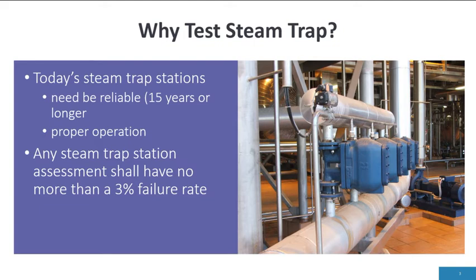So why test steam traps? Steam trap stations need to be reliable — 15 years of operation or longer at any pressure lower than 300 psi — and they also have to have proper operation. Any steam trap station assessment should have no more than a 3% failure rate, and to get to that low of a failure rate, you need to test and also do root-cause analysis.